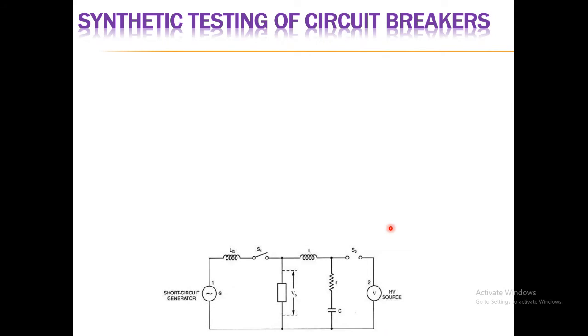As shown in the circuit diagram, there is a short circuit generator intended to produce the short circuit current, and one high voltage source used to produce the higher voltage stress across the circuit breaker when the short circuit current is interrupted by the circuit breaker.